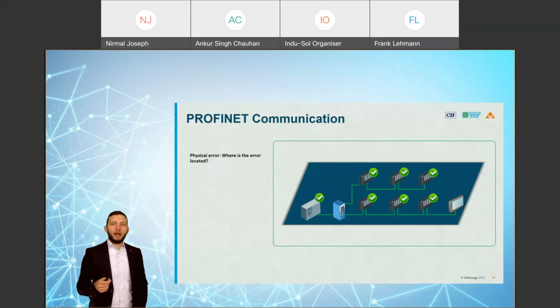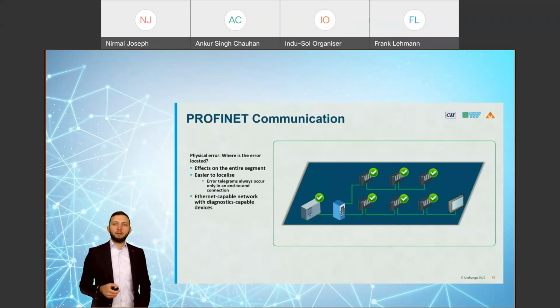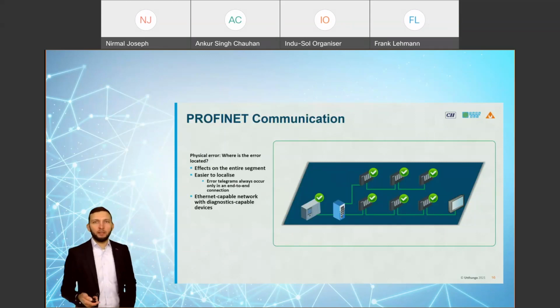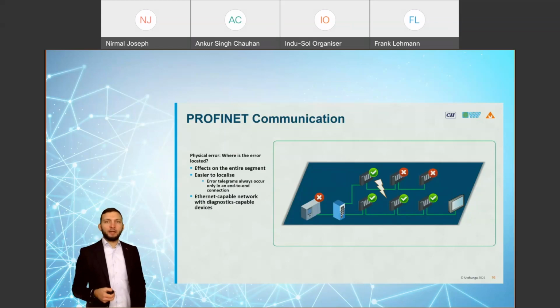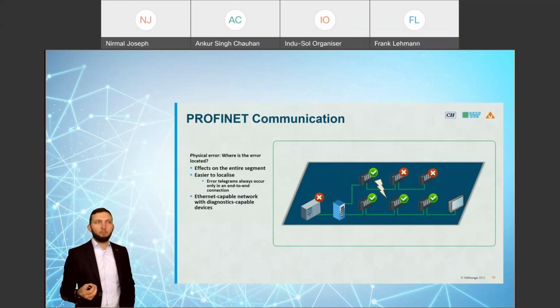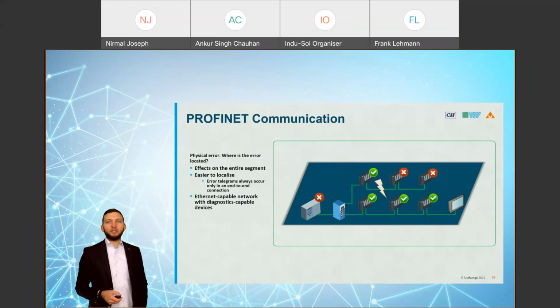Now let's go to the PROFINET world. We've learned there's a line structure between the single devices, and the termination is inside the devices. Therefore, if I have a physical error in a line, I don't interrupt the whole communication in my network - only the communication with the devices behind this line is interrupted, because I have separated physical lines in my Ethernet-based network. I think this is a big benefit of using PROFINET or Ethernet-based networks: on the physical side, I can quickly find bad cables or bad connections.